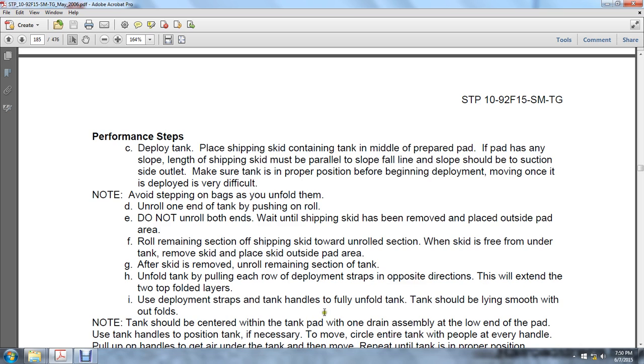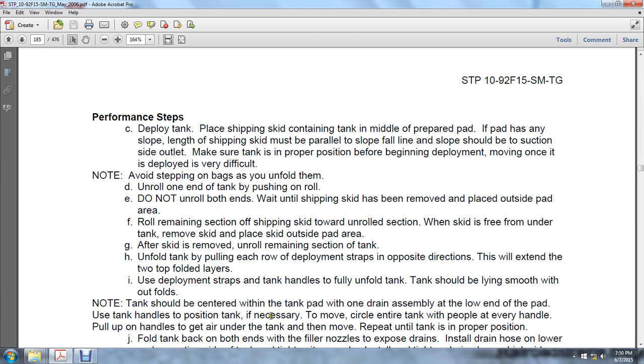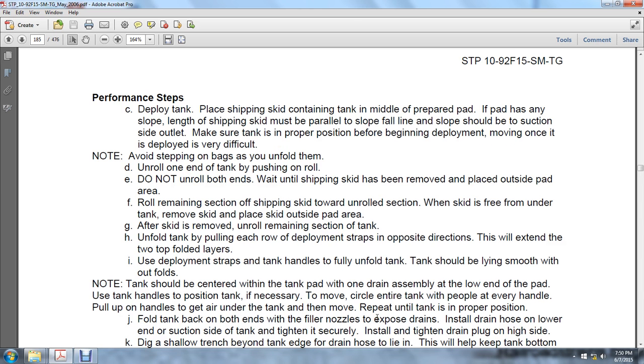The tank should be centered on the tank pad with one draining assembly at the low end of the pad. Use the tank handles on the top if necessary to move the tank, with people all around it at every handle, pulling on the handles to get the air out and move the tank. Repeat until the tank is in the proper position. Fold the tank back on both ends with a filler nozzle to expose the drains.